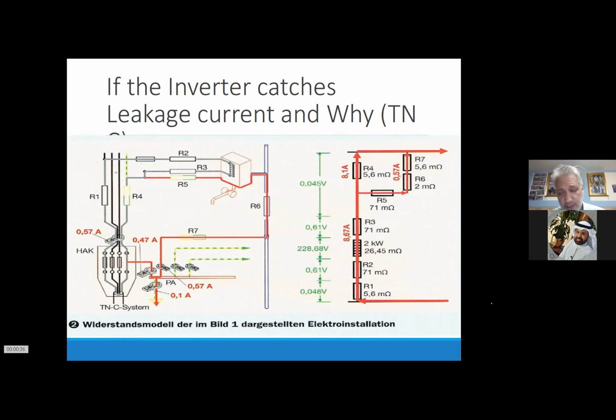heating in Germany. At that time, everything was metallic pipes. You have these individual leakage currents. So, when you have these systems, it travels everywhere. It can go down a stairway ladder from the roof. You can measure sometimes 500 milliamps or more, instead of wiring down with a PE.